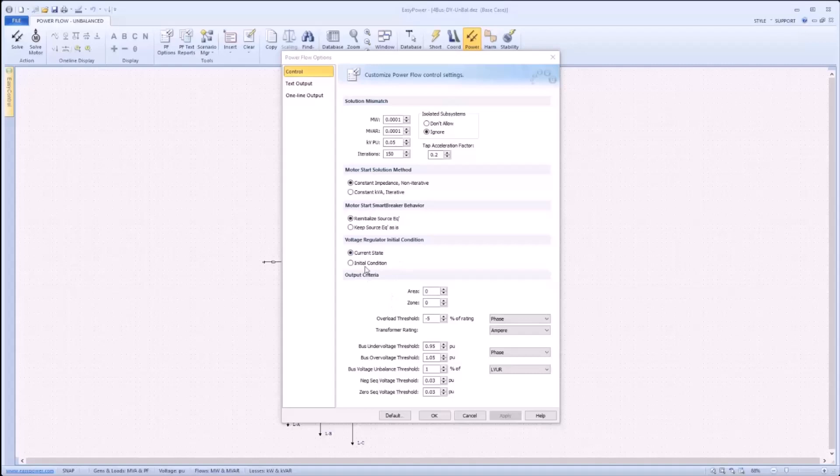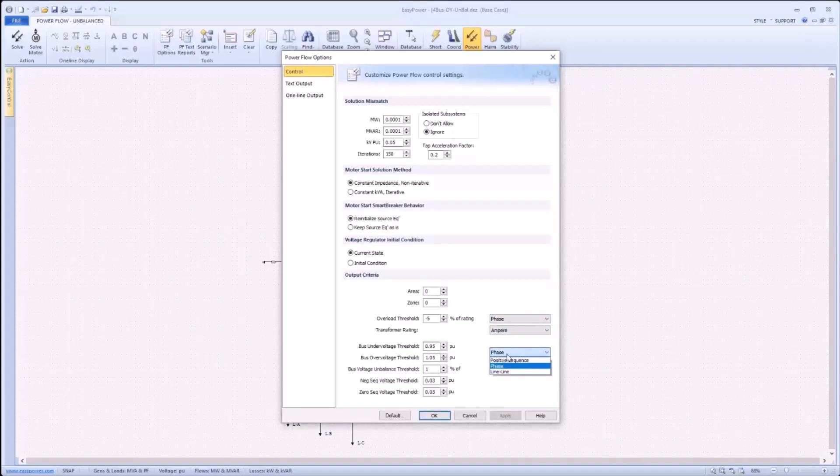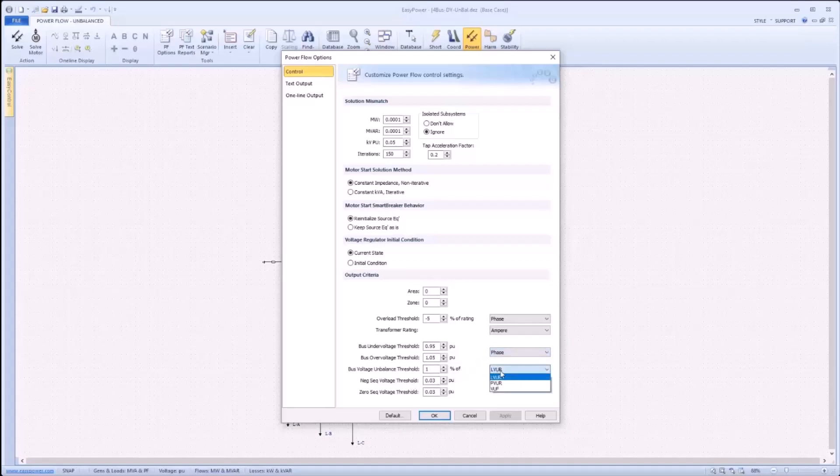Taking a closer look at the output criteria, one can see that overload thresholds as well as voltage thresholds can be specified. In addition, these thresholds can be specified further based on the desired type of comparison. For example, the overload threshold can be set to either positive sequence or phase. Positive sequence uses only positive sequence values to make the comparison, where phase uses the individual phases to compare to one another. Bus under voltage and over voltage thresholds can also be specified with these similar options, positive sequence and phase, as well as the addition of the line to line option, which uses, as the name suggests, line to line quantities to compare to the threshold specified. In addition, there's a bus voltage unbalanced threshold with standard calculation options to compare phases for unbalance. And finally, negative sequence and zero sequence voltage thresholds for comparison.